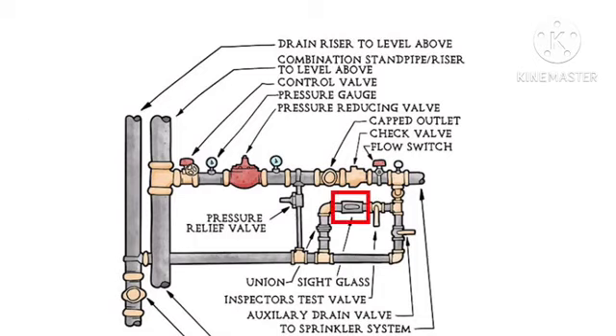Sight glass enables easy verification of water flow for the inspector's test. Floor control valve. Must be accessible, electrically supervised or locked, signage must be provided, and shall be tested annually. Water flow switch is used in wet sprinkler systems to detect the flow of water and to send an alarm signal.